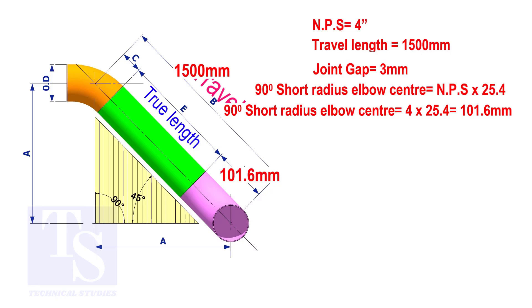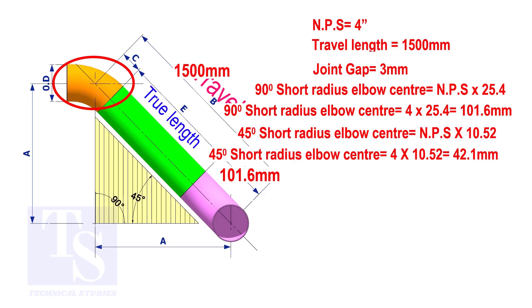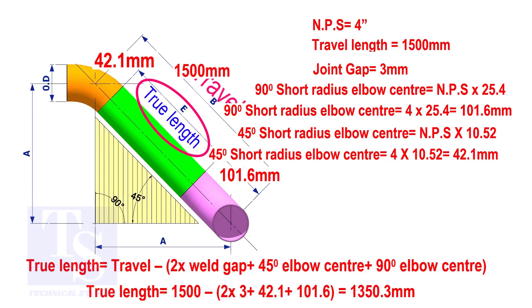To calculate the elbow center of a 45 degree short radius elbow, multiply the nominal pipe size by 10.52. The answer is 42.1 millimeters. To calculate the true length of the pipe, subtract two weld gaps plus both elbow centers from the travel length. The true length of the pipe is 1350.3 millimeters.